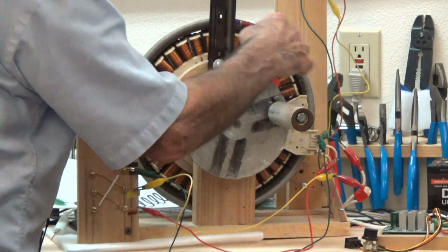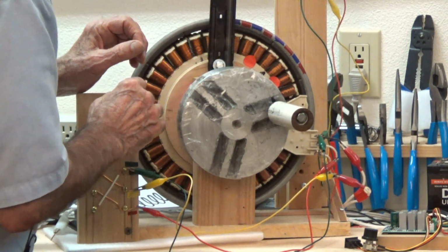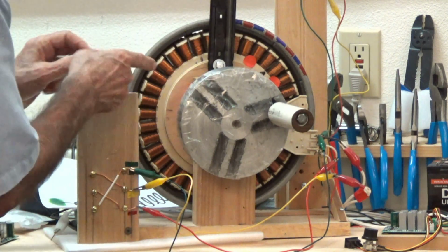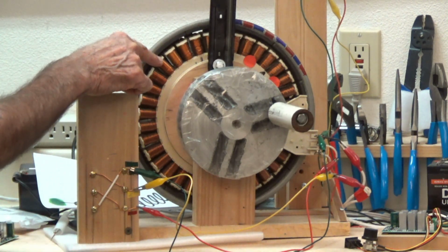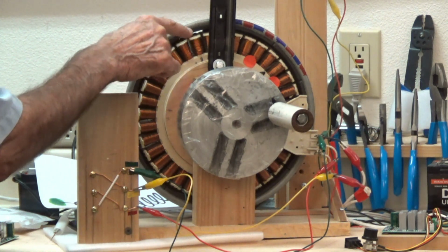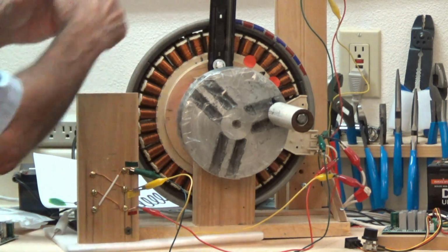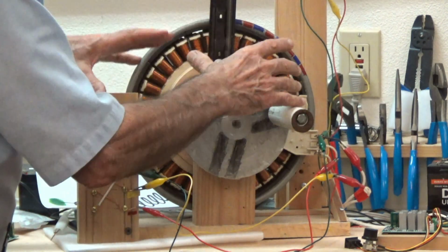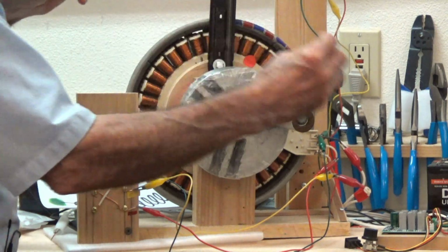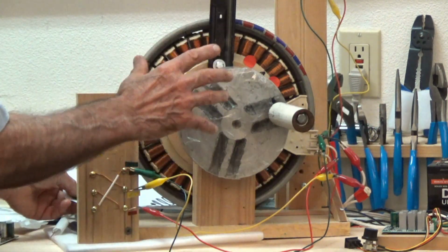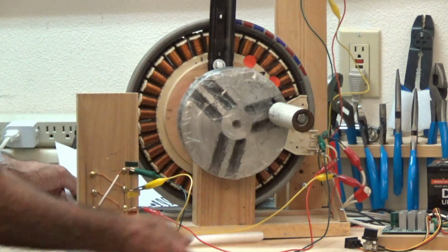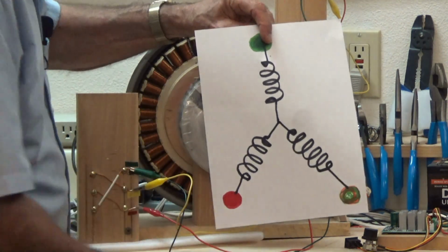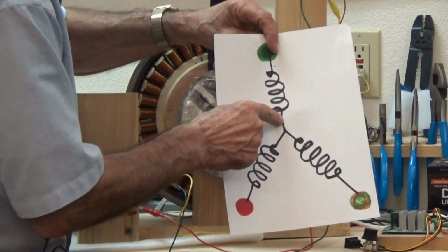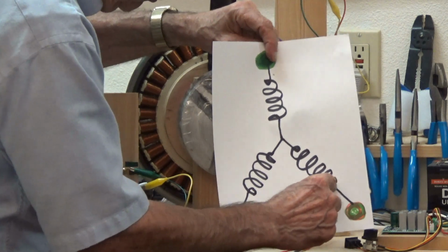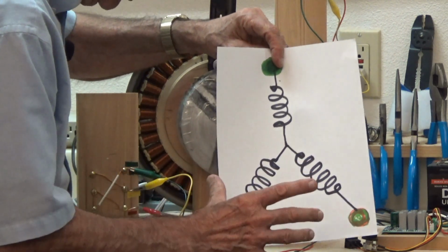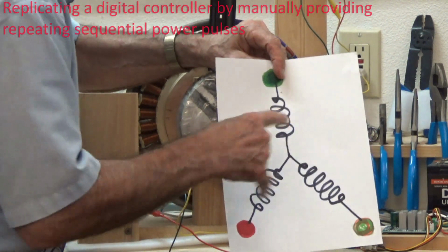On the inside are a bunch of coils of wire. It's a three-phase motor. So it's like, let's say this is phase 1, phase 2, phase 3, phase 1, phase 2, phase 3, and that continues all the way around. Those coils, all the phase 1s are tied together in series, all the phase 2s are connected in series, all the phase 3s are connected in series, and then they are connected like this. This represents all the phase 1s in series, all the phase 2s, and all the phase 3s, and then we're going to energize it across here, and across here.